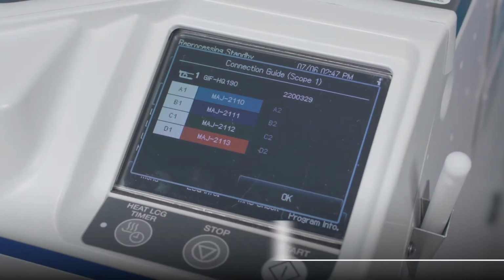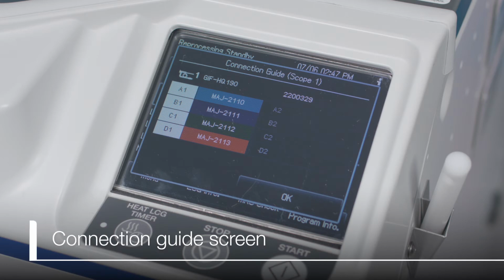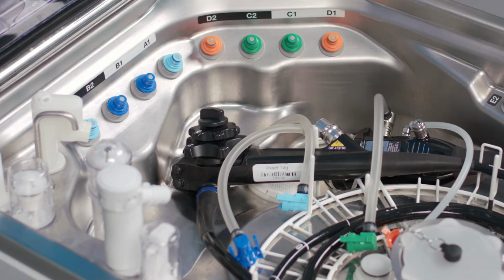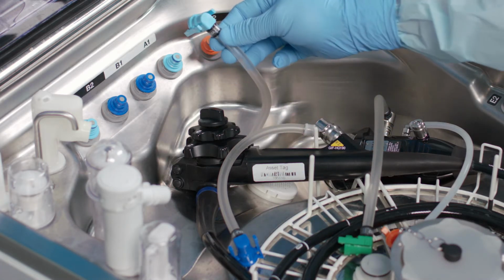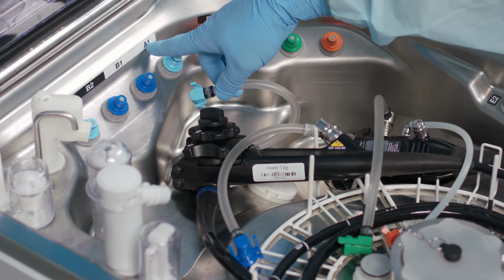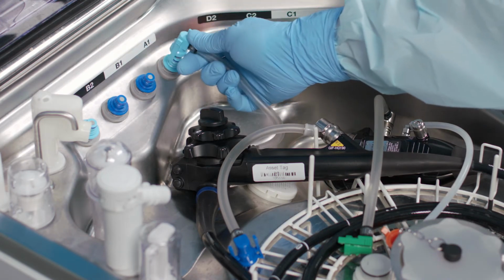If activated, once the scope RFID is scanned, the scope connection guide will appear on the display. This guide screen provides the information about the type of connecting tubes required for the endoscope that you just scanned. It will also let the user know the location of the connectors that these connecting tubes are connected to. You'll then select the connecting tube that matches the endoscope by referring to the connection guide screen on the display, matching the color of the tube connector to the color and number of the OER-Elite connector.